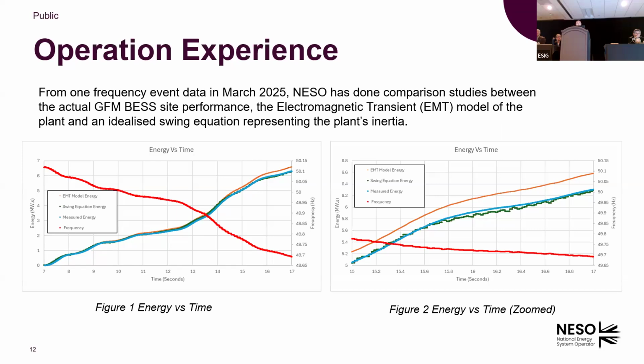inertia to the system. We did the simulation as well, based on the model they submitted. We also used some of the inertia numbers they provided, just looking at what kind of response you would expect from the grid forming battery if you use a simple swing equation. And we compared that with the site's real-time information as well. As you can see, everything aligns fairly well. So this means that this grid forming battery under this rate of change of frequency event behaved as we expected, providing inertia and support to the rest of the system.